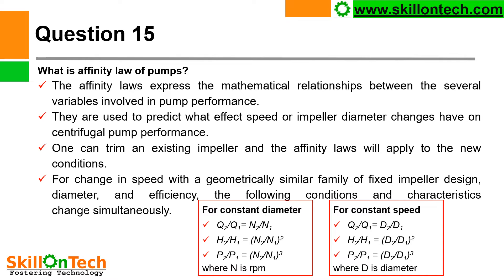For constant diameter: Q2/Q1 = N2/N1; H2/H1 = (N2/N1)²; P2/P1 = (N2/N1)³, where N is RPM. For constant speed: Q2/Q1 = D2/D1; H2/H1 = (D2/D1)²; P2/P1 = (D2/D1)³, where D is the diameter of the pump impeller. These are the important affinity laws of pumps.